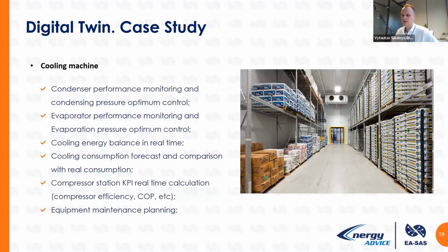So we set some KPIs for the compressor and the overall cooling machine, like coefficient of performance or compressor efficiency. And because we know these parameters every 5 minutes, we can understand the status of the machine in general and the energy consumption of your factory, and we can plan equipment maintenance.